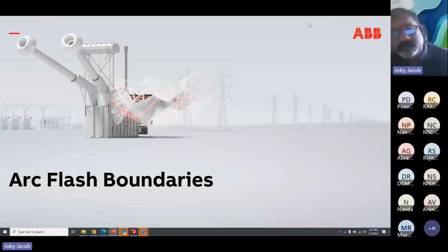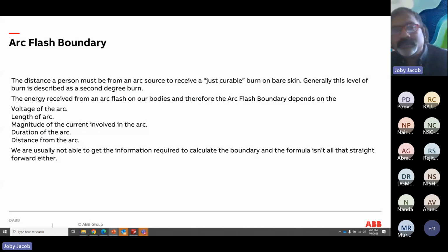Yeah, arc flash boundaries. This is the distance a person must be from an arc source to receive just a curable burn. If you are standing in front of a panel for any kind of switching, generally this level of burn is described as a second degree burn. If it's a curable burn, that's the area where you can stand, particularly when you are doing any job or work. Possibly that's the area where you can start working, right?